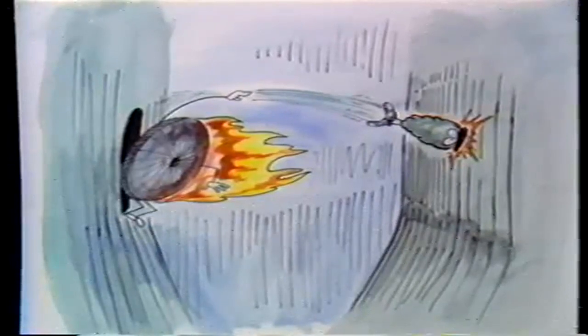Look for erosion as well as fuel accumulation to detect fuel impingement. Another case of fuel impingement is faulty burners that throw unburned fuel across the furnace. If you find fuel impingement, you're likely to find flame impingement as well, so be on the lookout for both.